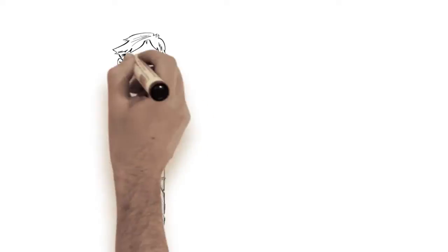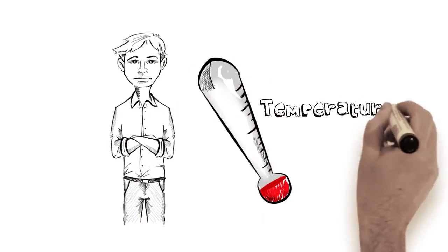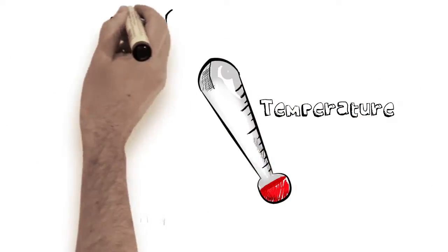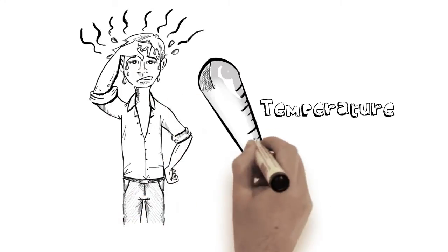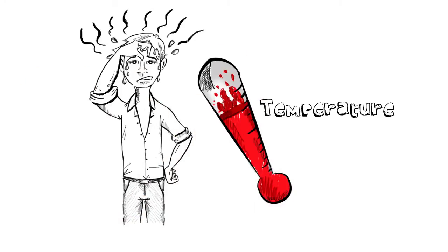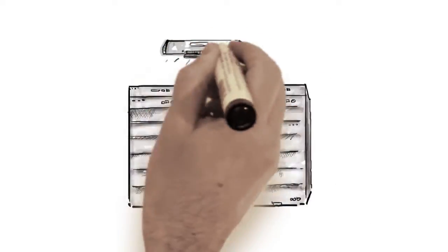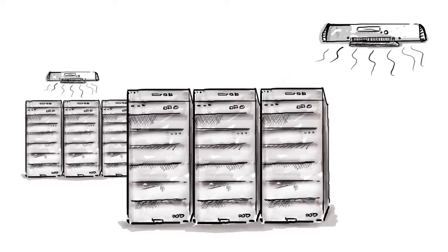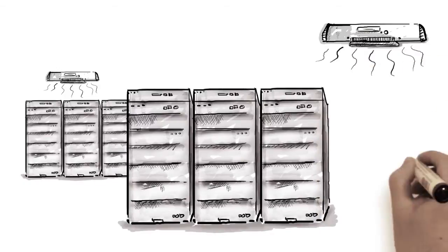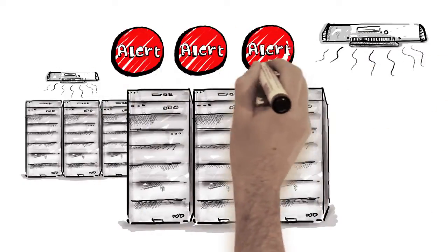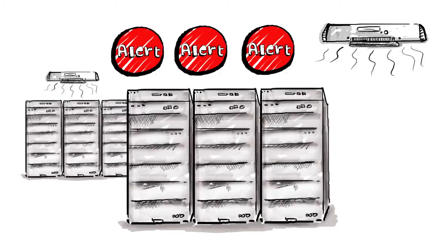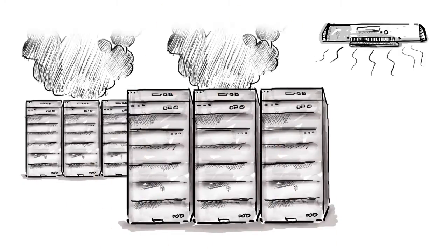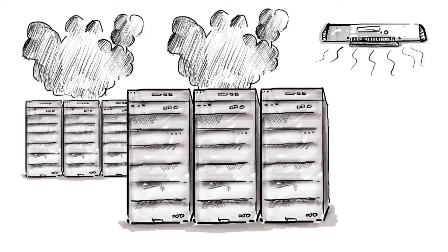This level of monitoring will alert you when air conditioning units start failing. Temperature should be between 18 to 27 degrees Celsius or 64 to 81 degrees Fahrenheit. Only doing ambient temperature monitoring isn't enough, though. You could already face an earlier heat issue in your server racks that goes undetected as it is initially being compensated by the aircon. Only when the aircon can't cope anymore will you get alerted. At that point, it may already be too late for your equipment.